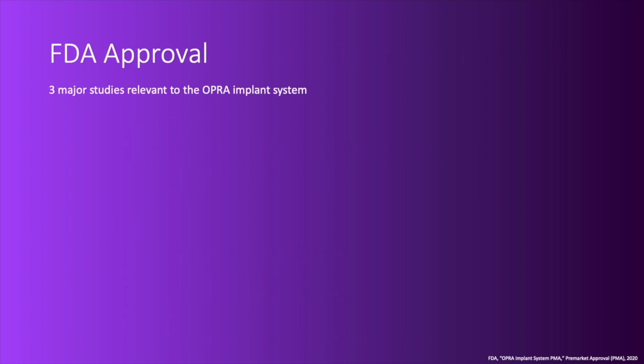The OPRA implant system was approved by the FDA for pre-market approval on December 18, 2020, after 2 years of amendments and after 5 years of FDA approval under a humanitarian device exemption, with 6 years of previous amendments. An ongoing FDA pre-market approval study is currently active through clinicaltrials.gov, evaluating the efficacy of the OPRA device.